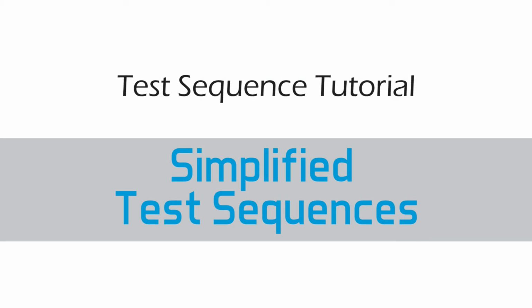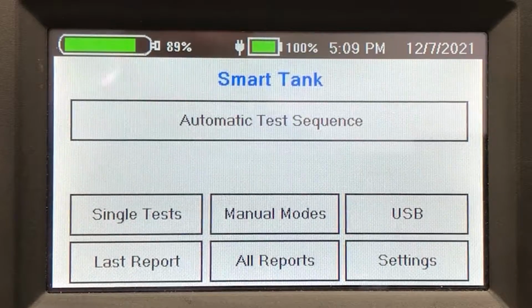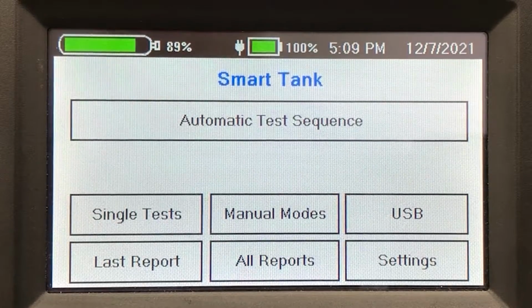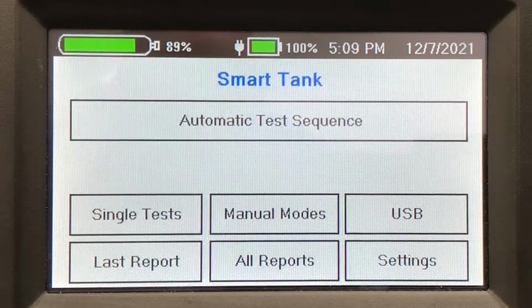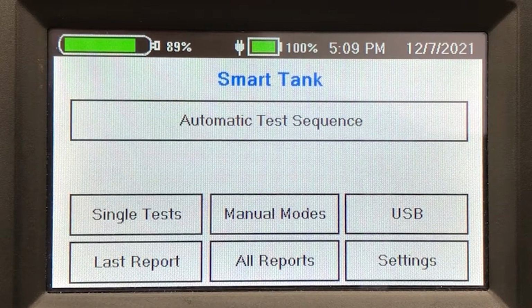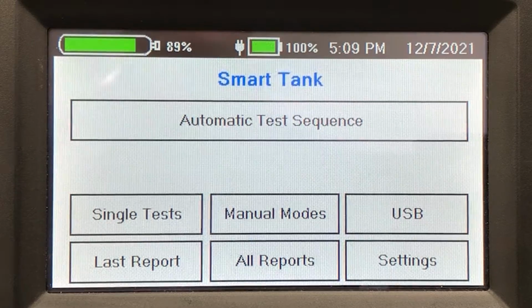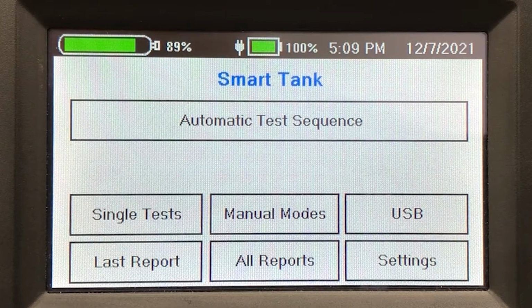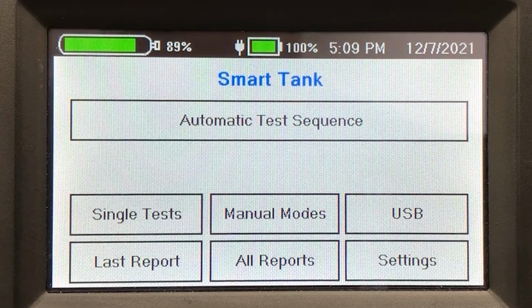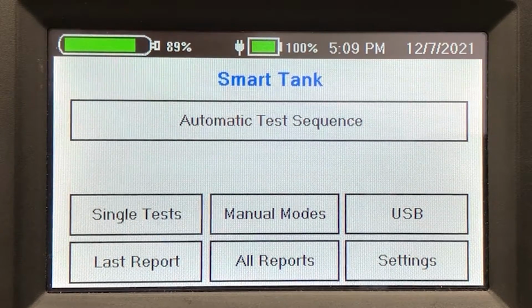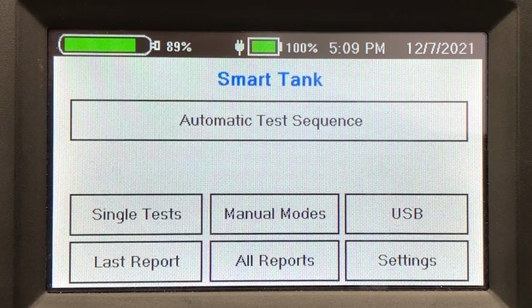This video is about simplified test sequences. Some of the manufacturer's recommended functional checks can be very time consuming. Because of this, some of our customers use an AEM or alternative equipment maintenance program with simplified test sequences. To help you set up your AEM, we've provided simplified test sequences which typically include only calibration steps and functional alarm checks.